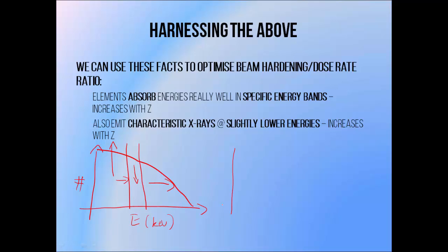This isn't the most accurate depiction of the effect of these two processes on a beam energy spectrum, but what I'm trying to emphasize here is that within the range of increased absorption, which we call an absorption edge, the number of photons has been decreased. Now it will be decreased everywhere, but more so in this part of the spectrum. And at a slightly lower energy due to characteristic X-ray emission, the number of photons hasn't been decreased as much. So the lower energy end of the spectrum will still be filtered out to a certain degree, but it's added to somewhat as well by the characteristic X-ray emissions within the filter.